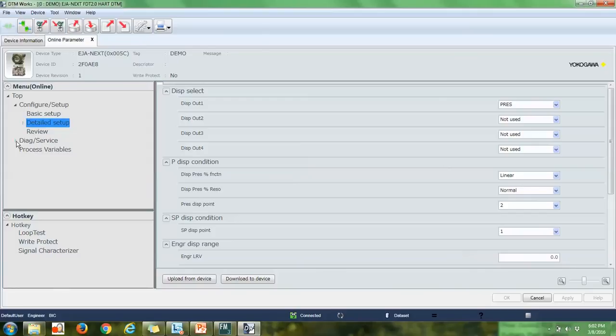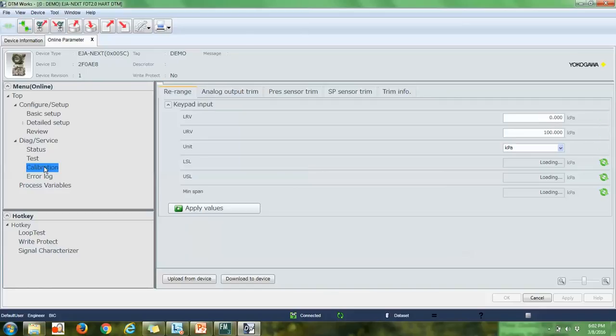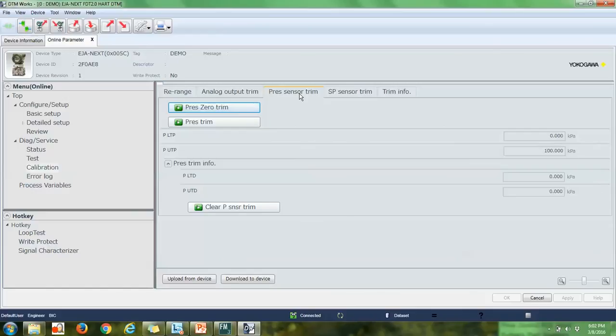Under Diagnostics and Service, and under Calibration is where you'll find the pressure trim. So we're going to go to Pressure Sensor Trim. Right here we have the values that the capsule is set to. We scaled it to 0 to 100 kilopascals. And then we have our trim information. Right now this transmitter has not been trimmed, so no values have been adjusted. We're going to do a zero and a full scale trim.